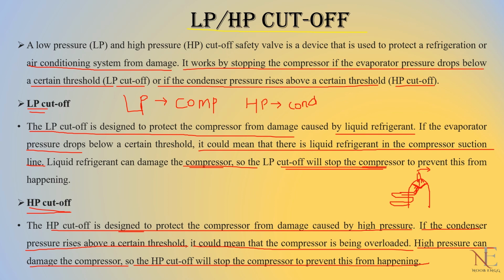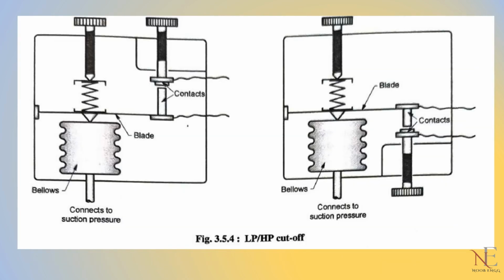So the working of both the devices, HP and LP, is to stop the compressor when there is a high pressure or a low pressure. Now how does it do this? Let's see. This is a diagram I have taken from the book itself because there were no diagrams available on the net. This one is for high pressure, and this is for low pressure. Now let me tell you the components here. These are the bellows. They are nothing but a type of moving plates. These are the plates you can see here.